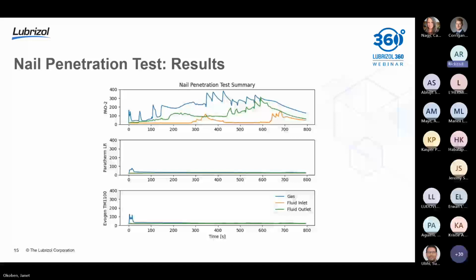We executed this test by nail penetration. A metal bar penetrates the module and goes about halfway through the first cell. This initiates that thermal runaway event in the initial cell. The goal here is to see just how good some of these immersion coolants are in preventing thermal runaway, by providing sufficient thermal heat transfer away from that first cell to prevent any of that excess heat generated by the gases developed during the thermal runaway event from spreading to the second, third, fourth, and other cells in the pack.